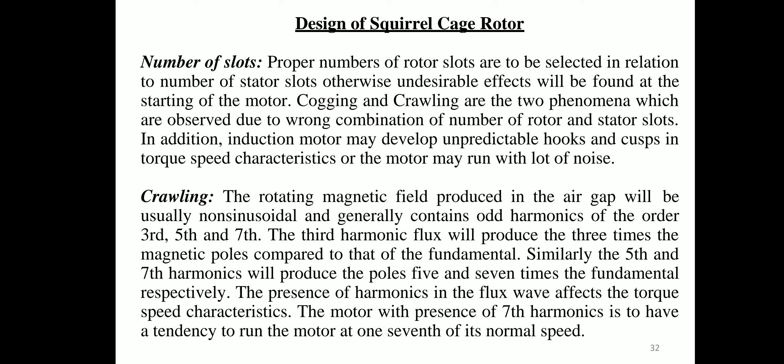The rotating magnetic field produced in the air gap is generally non-sinusoidal and contains odd harmonics of order third, fifth, and seventh. The third harmonic produces three times the magnetic poles of the fundamental; fifth and seventh harmonics produce five and seven times respectively. The presence of seventh harmonics tends to make the motor run at one-seventh of its normal speed.